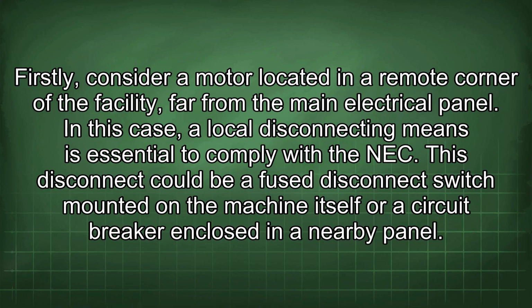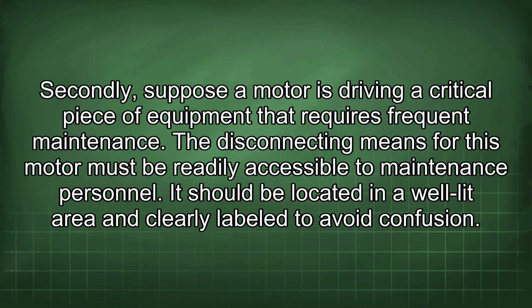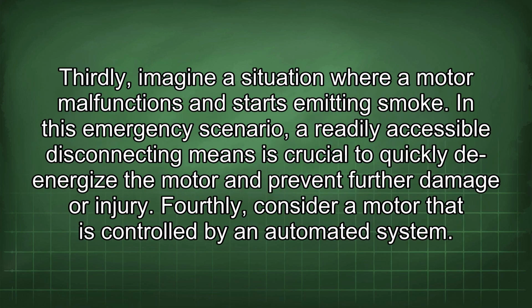Secondly, suppose a motor is driving a critical piece of equipment that requires frequent maintenance. The disconnecting means for this motor must be readily accessible to maintenance personnel. It should be located in a well-lit area and clearly labeled to avoid confusion. Thirdly, imagine a situation where a motor malfunctions and starts emitting smoke. In this emergency scenario, a readily accessible disconnecting means is crucial to quickly de-energize the motor and prevent further damage or injury.